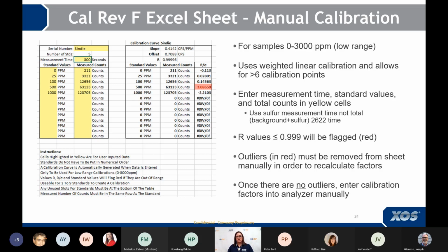The other thing I like about this sheet is you can see the R value and the residuals, you know, before they get entered into the analyzer. So you can be aware that there's a bad point. So here in this worksheet, you'll see it flagged there in red. And then once you get the calibration you like, so you would then rerun that point, that bad 500 ppm point, put the new counts values in, and once you're happy with that, you would enter the calibration factors into the analyzer using manual calibration.